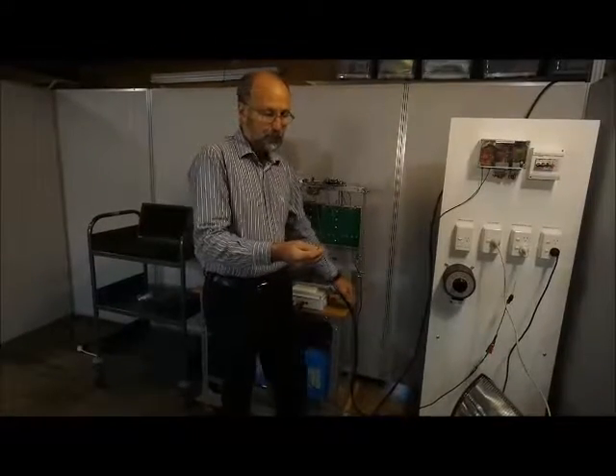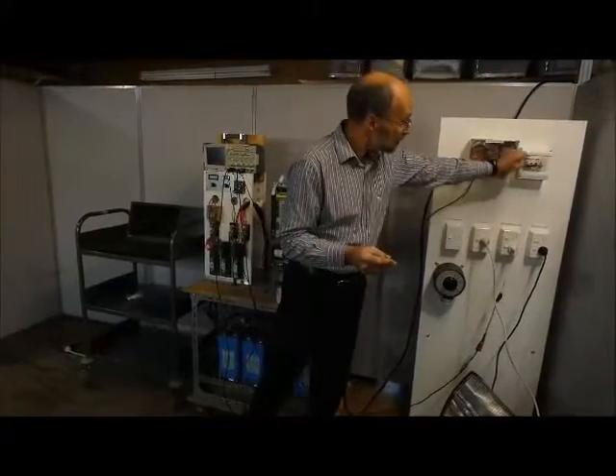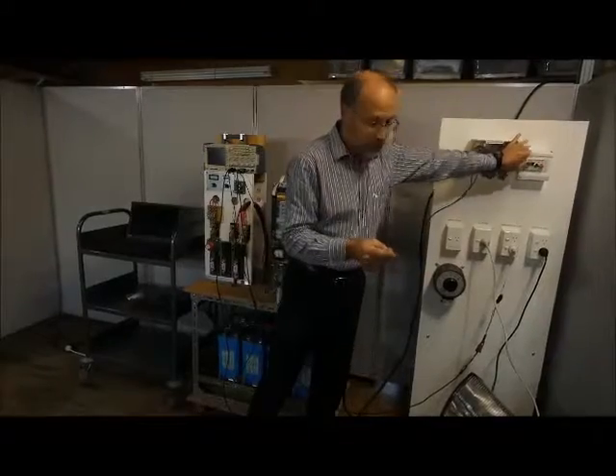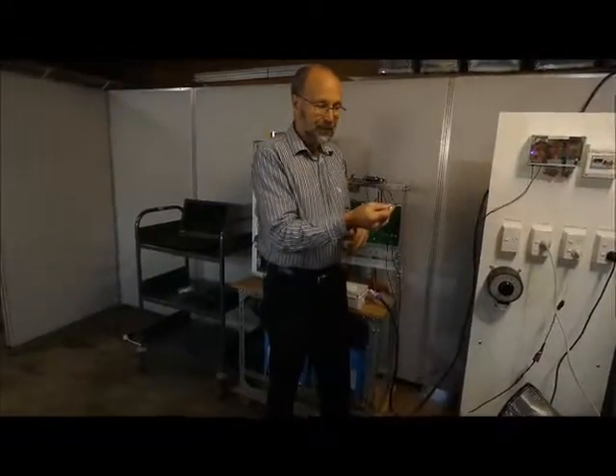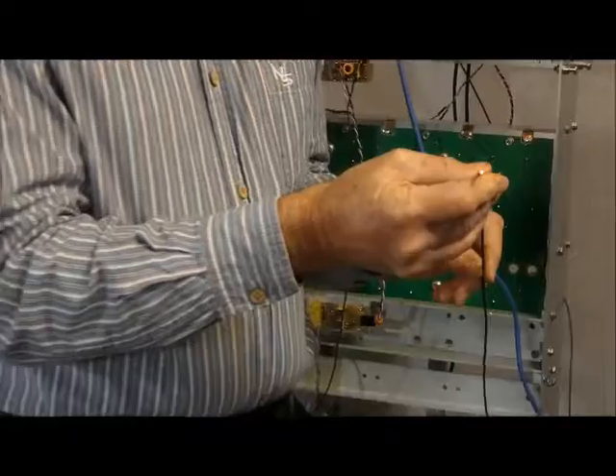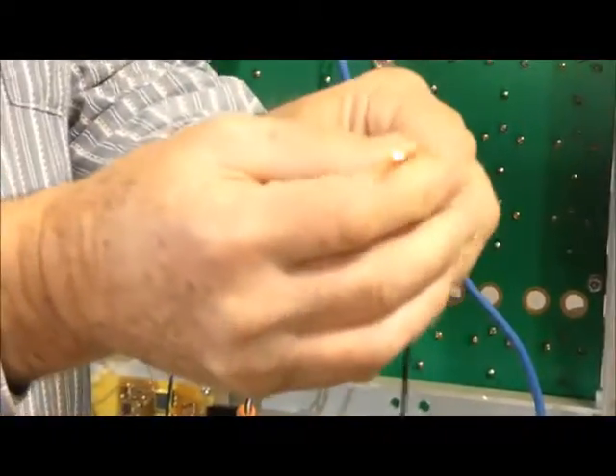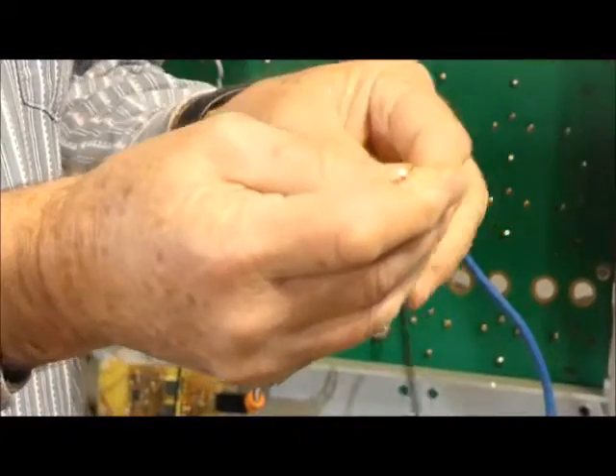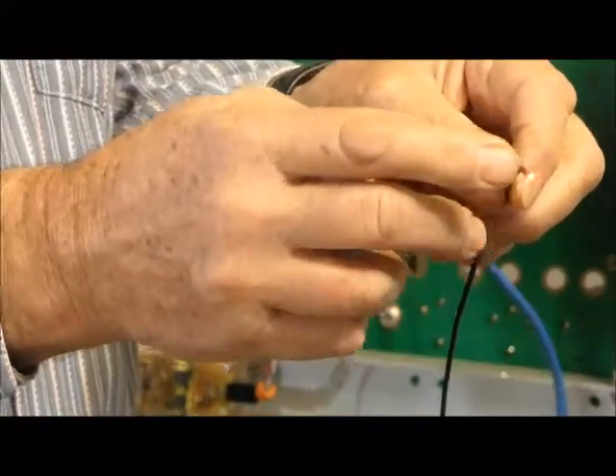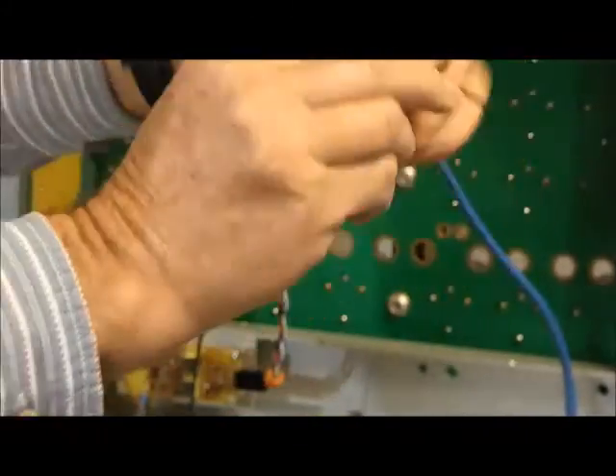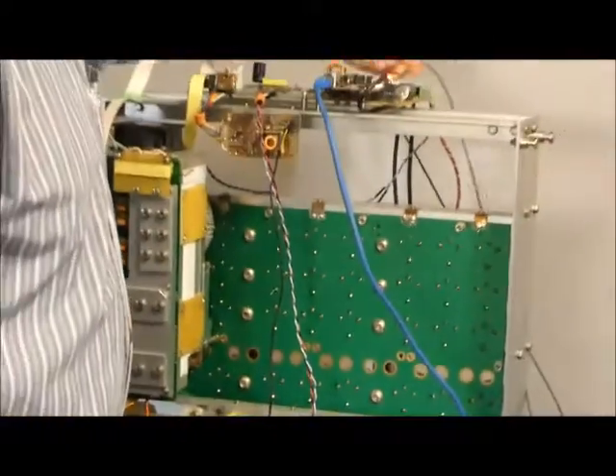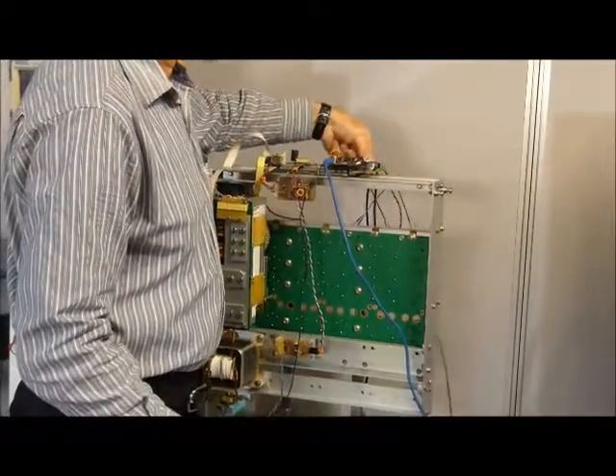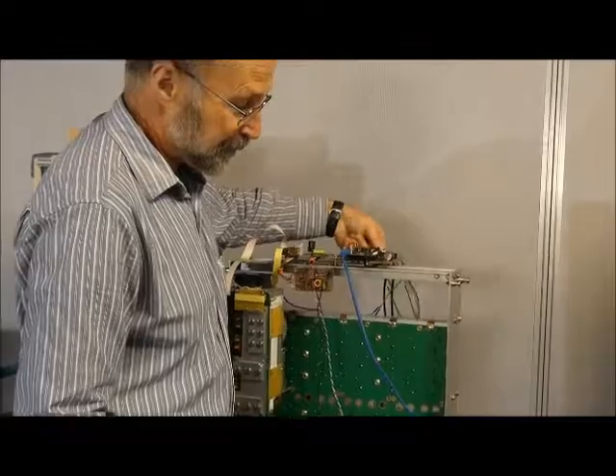If we turn on the grid interface, you'll see the red light coming along the cable, which is the data coming from the grid interface back to the inverter. This is a good way of working out which cable is which. We know that that's the transmitter from the grid interface, so we plug it into the receiver on the inverter.